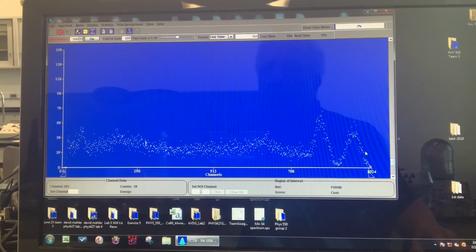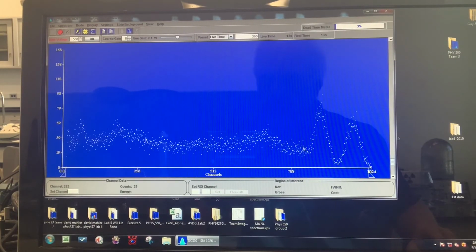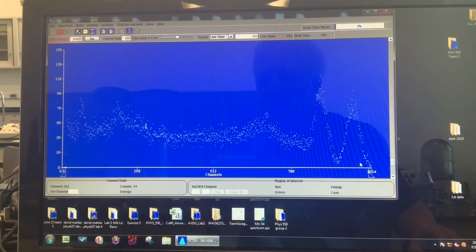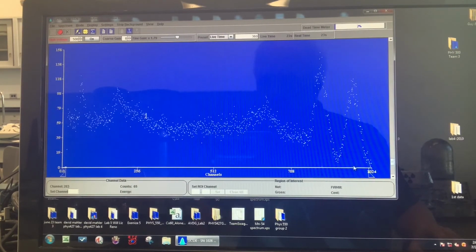So I can go ahead and multiply that by another factor of 2, but to be on the safe side, let's just guess something like 1.8. Okay, now, all right. So these are the two gamma energies coming out of the cobalt 60, and I made a pretty good guess for what the gain value should be to put this highest energy peak in the highest channel possible.